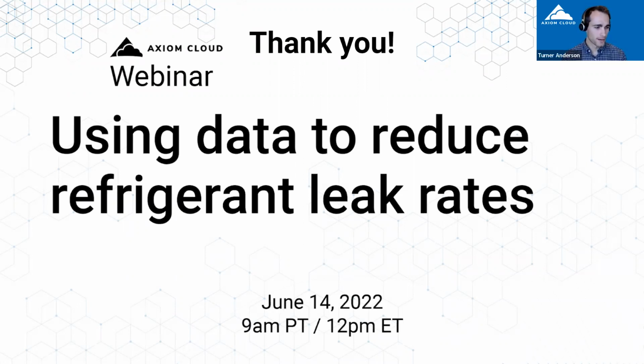We got a question about CARB requirements in California. This person is saying that in California, all stores have to have some sort of leak detection, or they have to do manual leak checks every 30 or 90 days, depending on the system size. Does having a system like that change those requirements at all? Or do you still have to have other leak detection methods?